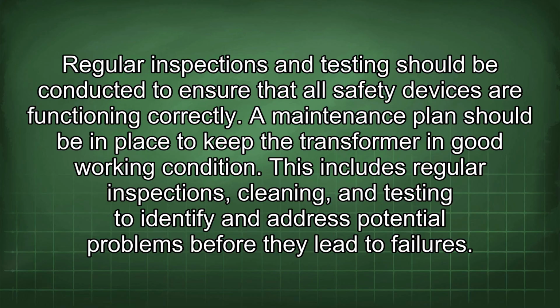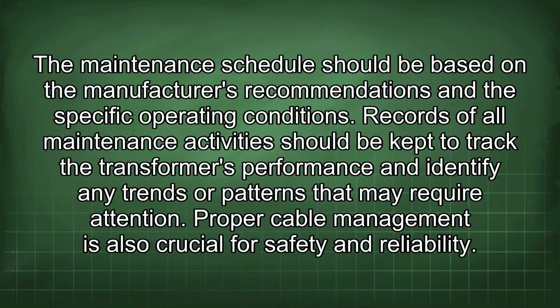A maintenance plan should be in place to keep the transformer in good working condition. This includes regular inspections, cleaning, and testing to identify and address potential problems before they lead to failures. The maintenance schedule should be based on the manufacturer's recommendations and the specific operating conditions. Records of all maintenance activities should be kept to track the transformer's performance and identify any trends or patterns that may require attention.